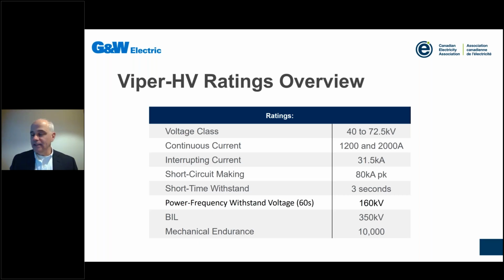One thing I'll point out on this slide is the mechanical endurance. We talk about maintenance-free platforms, the ability to not monitor things like oils or SF6, but also the capability of mechanical endurance. The ability to operate 10,000 operations in this voltage class is essentially unheard of. It doesn't necessarily mean the sub-transmission infrastructure will ever require 10,000 operations, but it's a sign of mechanical endurance, with the minimum amount of moving parts.